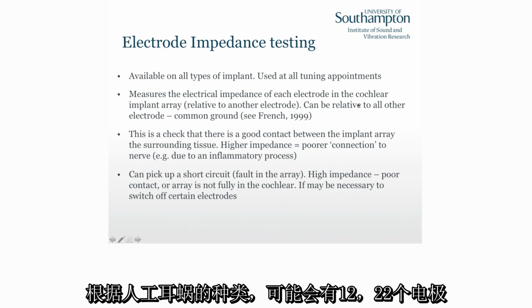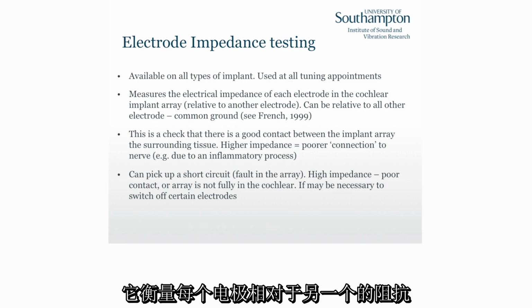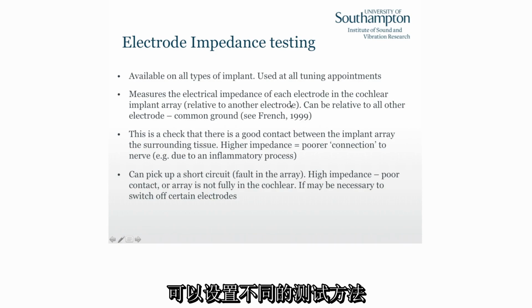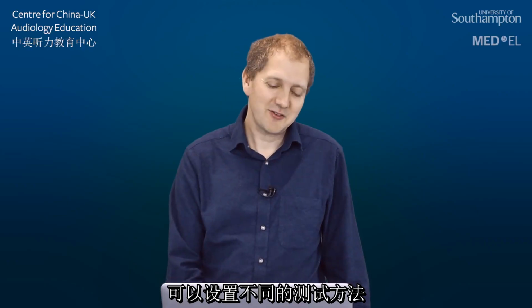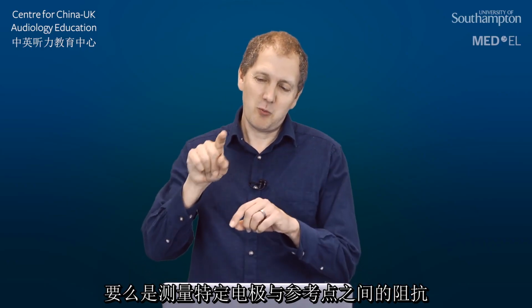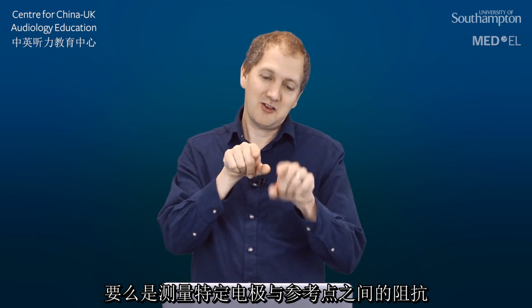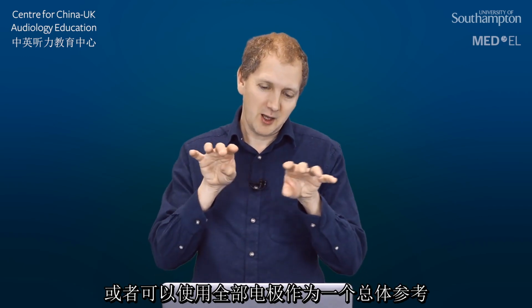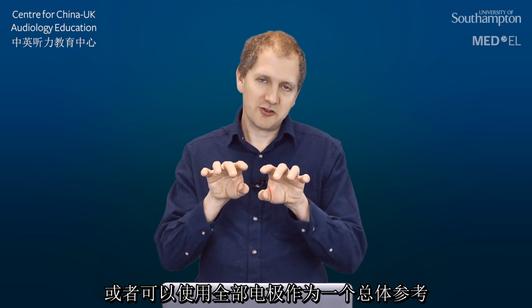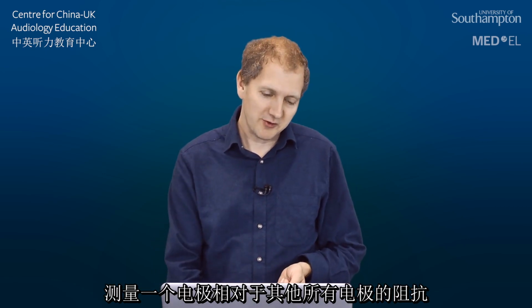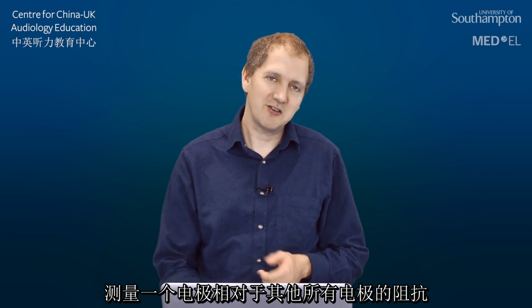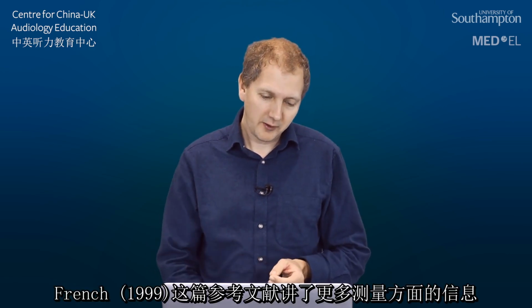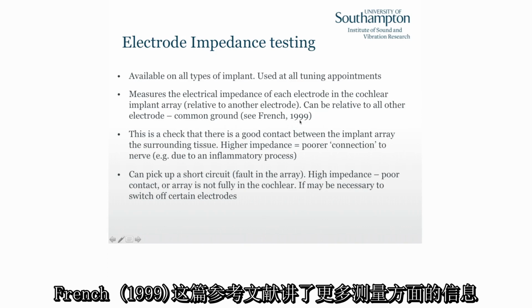Depending on the type of cochlear implant we have, we might have 12 electrodes or 22 electrodes, and it measures the impedance of each one relative to another one, or you can have different settings. It either measures from one electrode to some reference point, or you can use all the electrodes as a reference. So a common ground reference means you're using impedance relative to all of the other electrodes. There's some more information about how these things are measured in the reference here, French 1999.